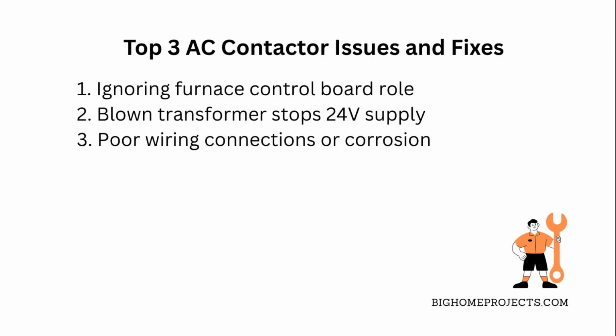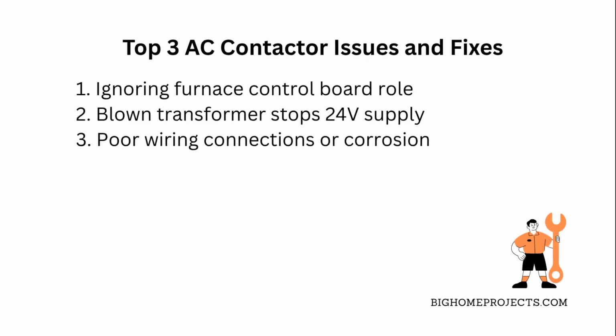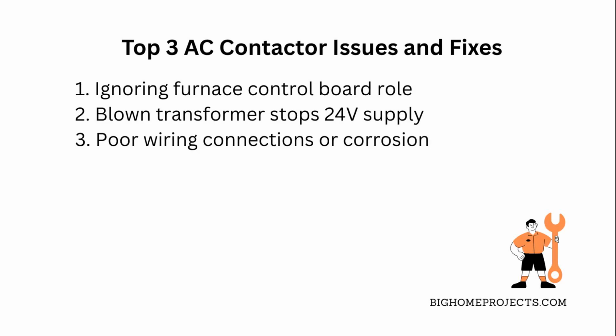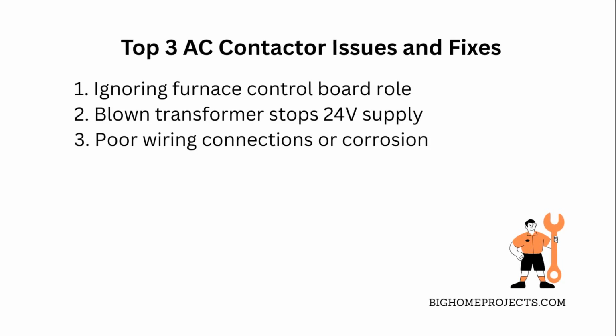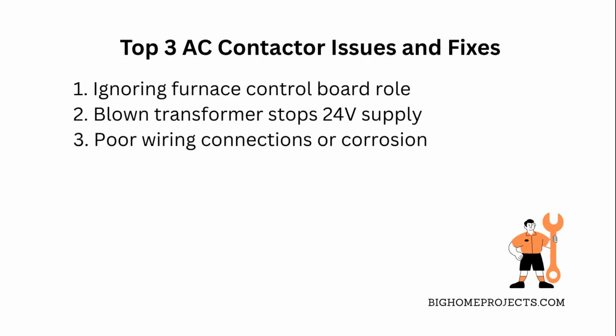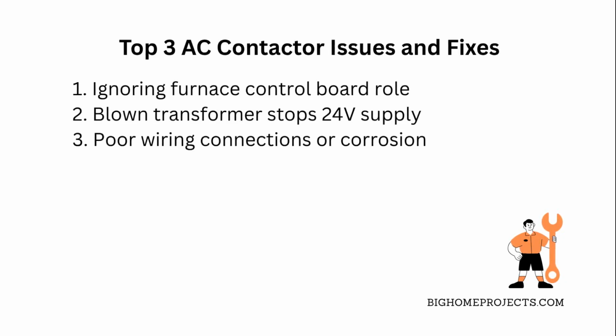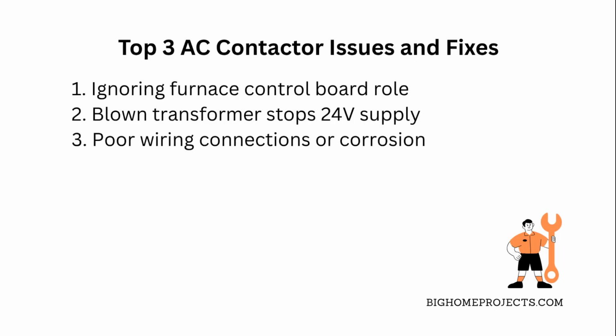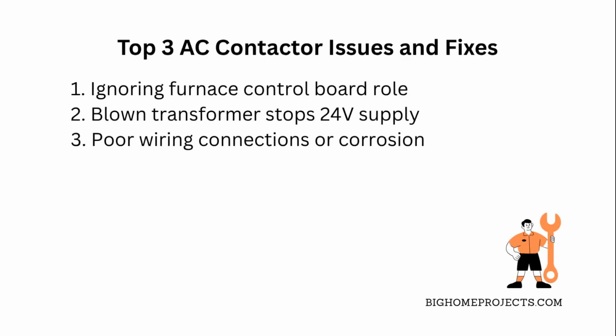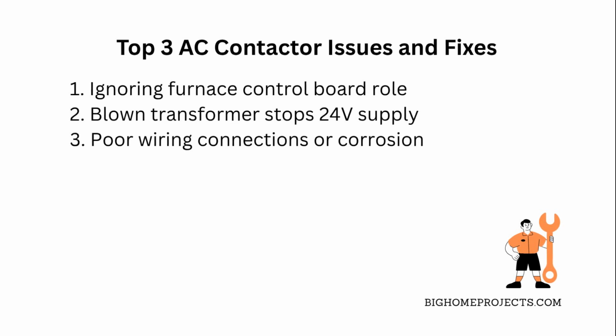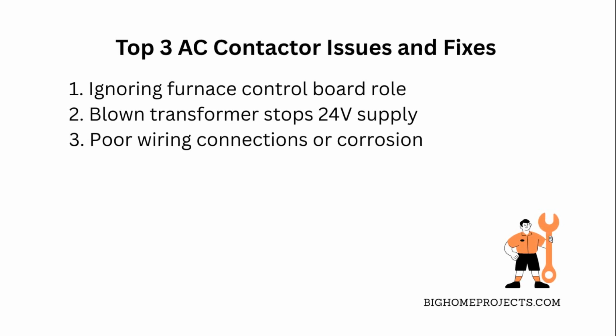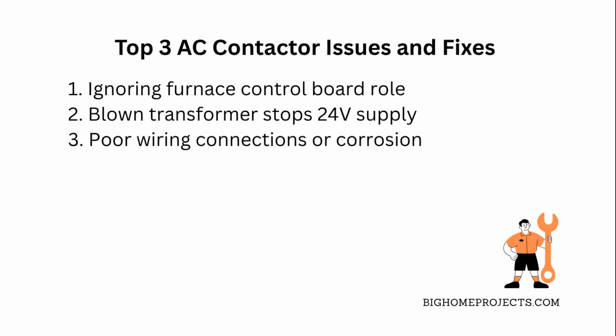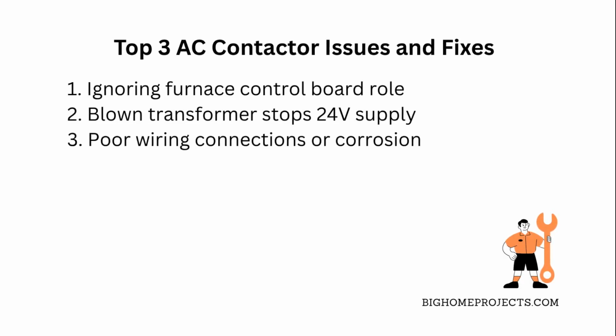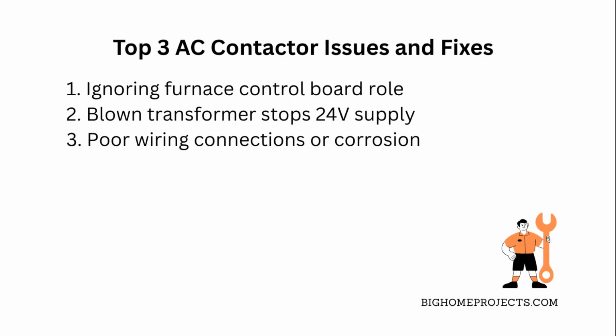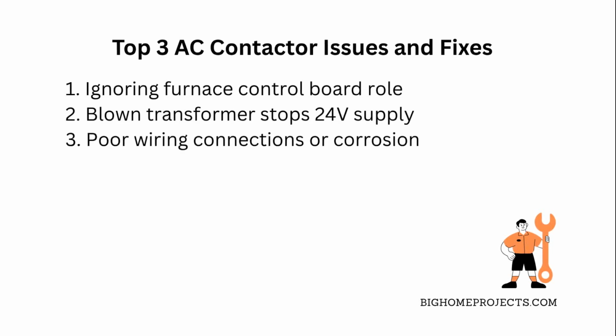your AC. One of the biggest mistakes people make with AC contactor issues is assuming the 24 volt supply comes directly from the thermostat, ignoring the control board's role. Fix that by tracing wires back to the furnace control board to be sure. Another common problem is ignoring blown transformers inside the control board that stop supplying 24 volts. Swapping out a faulty transformer usually clears this up. Lastly, folks often overlook poor wiring connections or corrosion at the contactor terminals, which can cause intermittent power loss. Cleaning and tightening these connections will usually fix that issue quickly.